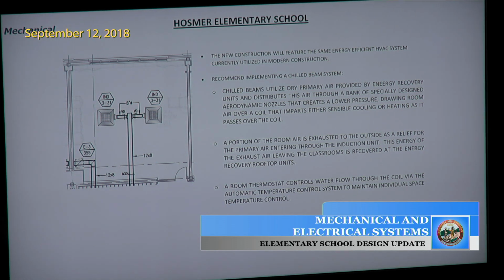One of the options for HVAC in the new classrooms is chilled beams, which we've used on a lot of projects. Basically a chilled beam is a device in the ceiling. Ventilation air is ducted into it, and through induction, it induces room air to cool or heat that room. We've applied this in a lot of schools in Plymouth, at Natick, and some Boston public schools. So that's an option for what the HVAC in a new classroom will look like. It's very unobtrusive, very quiet, with no moving parts in the classroom, and it meets all the LEED requirements.